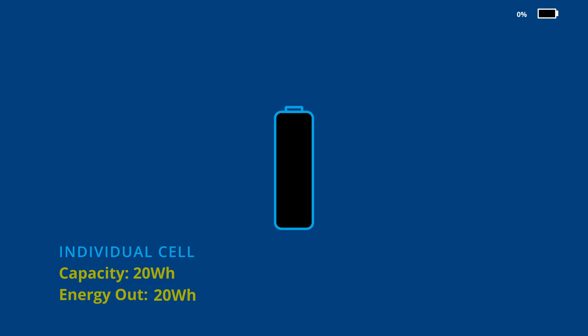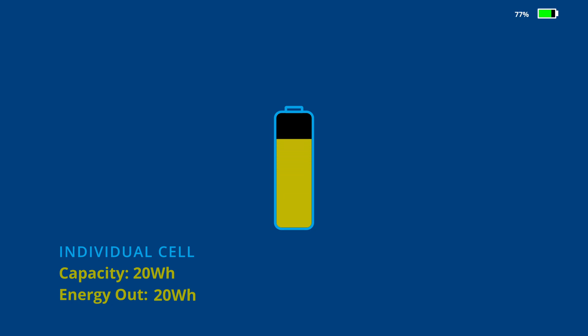Charging is achieved by driving current into the cell until the voltage corresponding to the 100% state of charge point is reached. Care must be taken to never exceed the upper and lower voltage limits of a single cell or irreversible damage will be done.